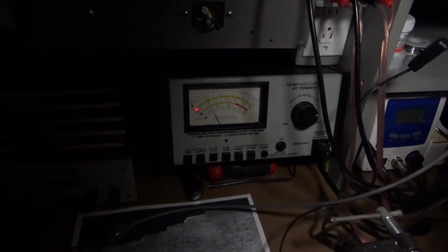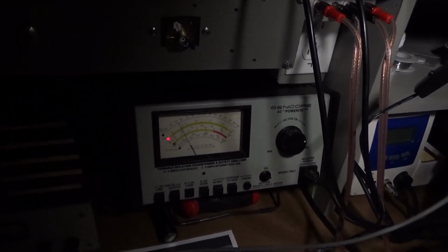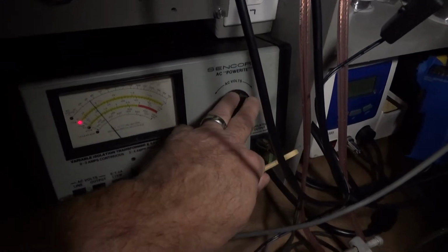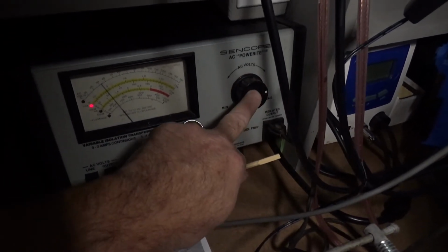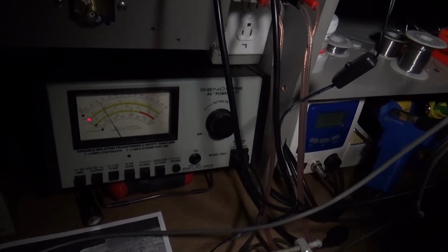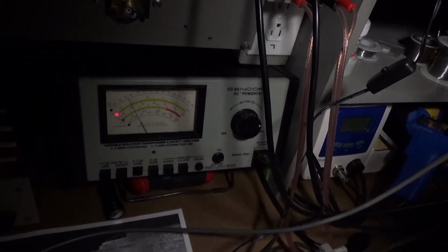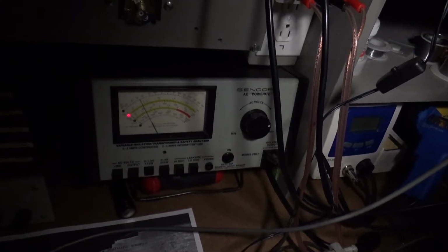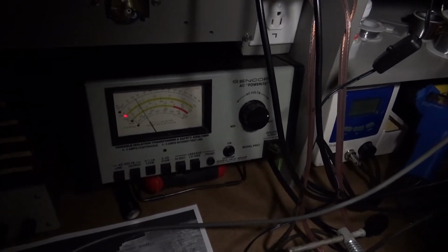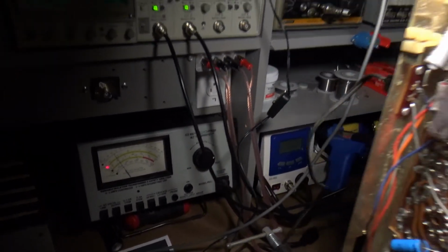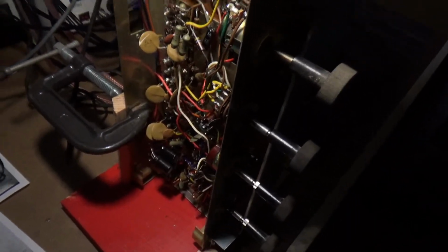And if you go to eBay or wherever and buy a variac, the variacs will adjust the voltage, and that's what this is. This knob here is a variac, but it does not isolate. A variac is nothing more than an autotransformer, which means you've got a common to the in and the out, first problem, and then your output is also not isolated. It goes through the autotransformer. Basically, a variable autotransformer is all it really is. So there's no isolation in a variac. You have to have an isolation transformer. There's lots of people out there. Just look up isolation transformer on YouTube, and you'll see 1,000 references to it. But anyway, just that little safety.